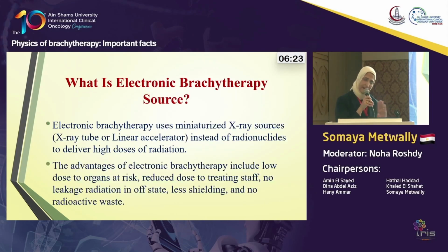So we don't have any isotopes. Electronic brachytherapy uses miniaturized X-ray sources. It is an X-ray tube or miniaturized linear accelerator inserted instead of radionuclides to deliver a high dose of radiation.